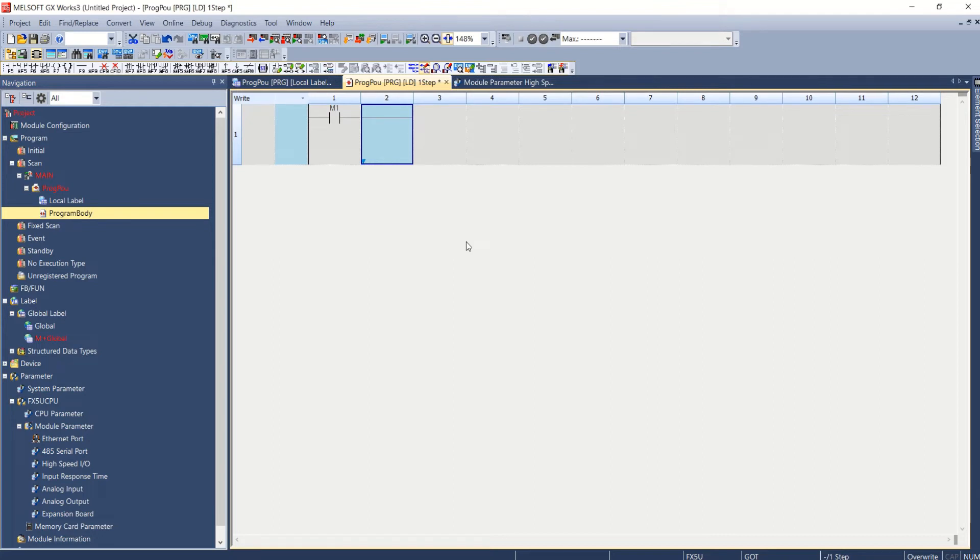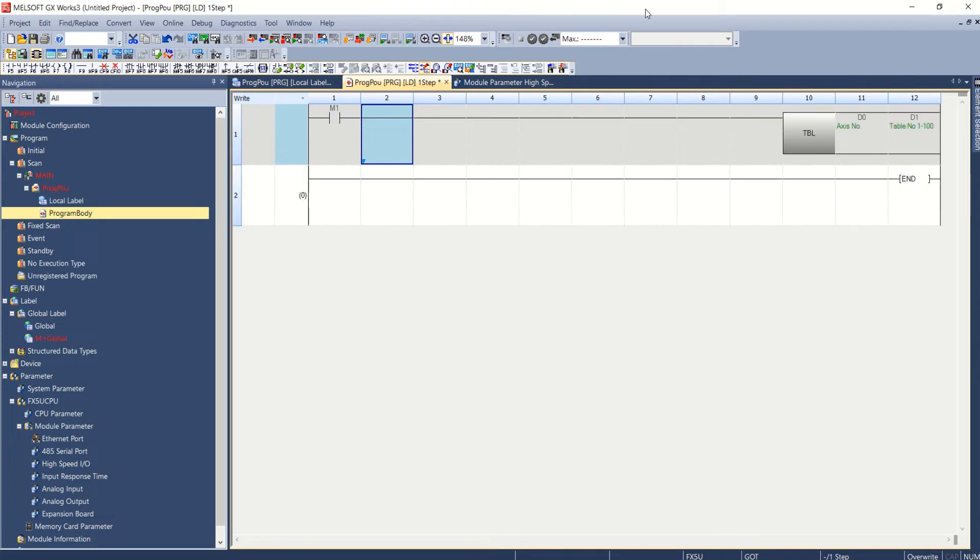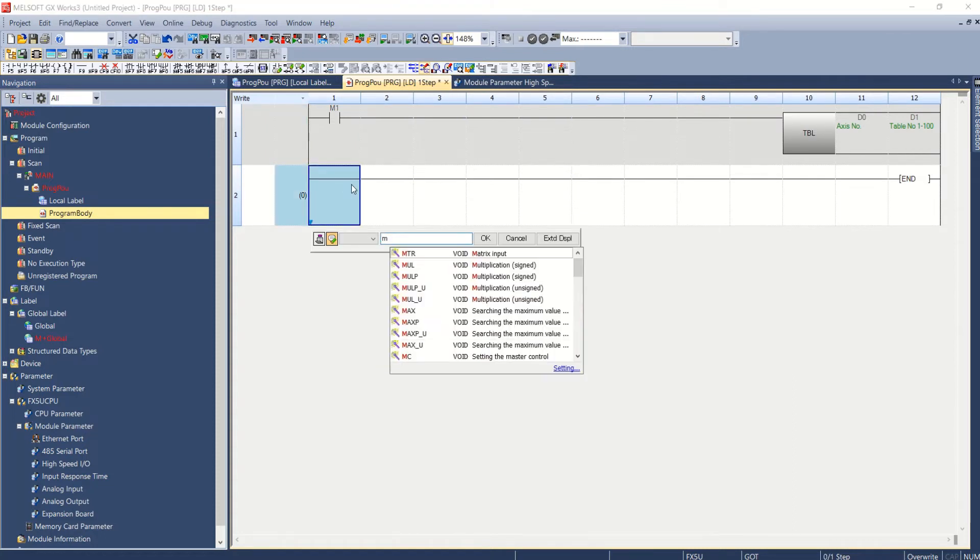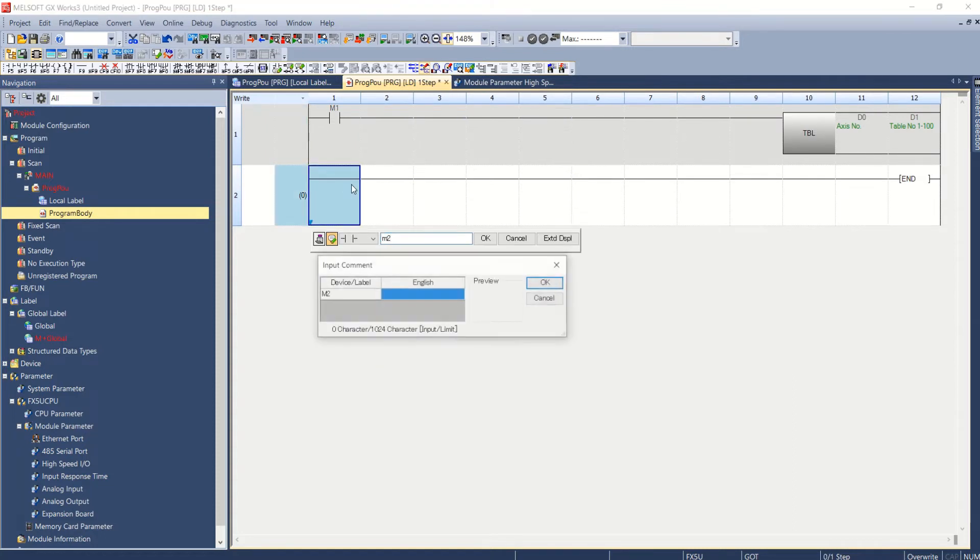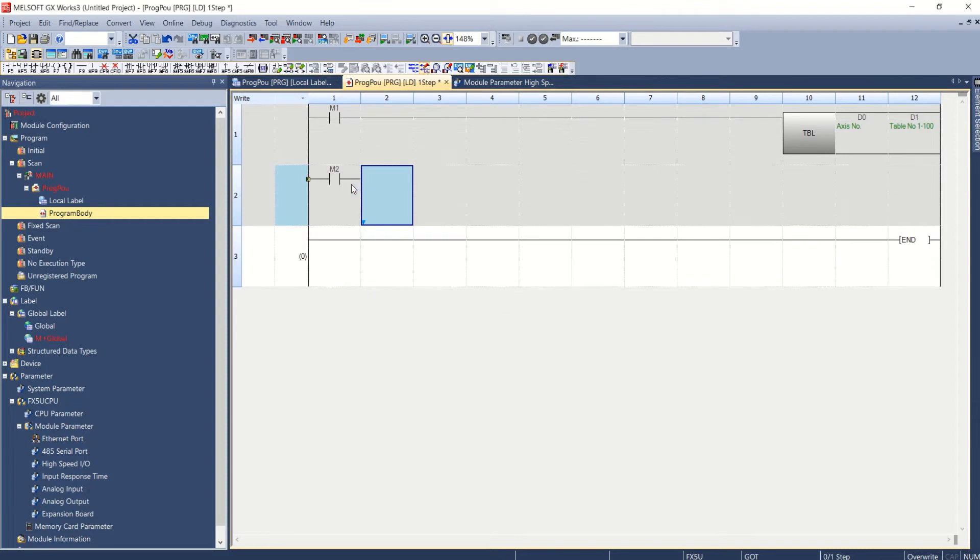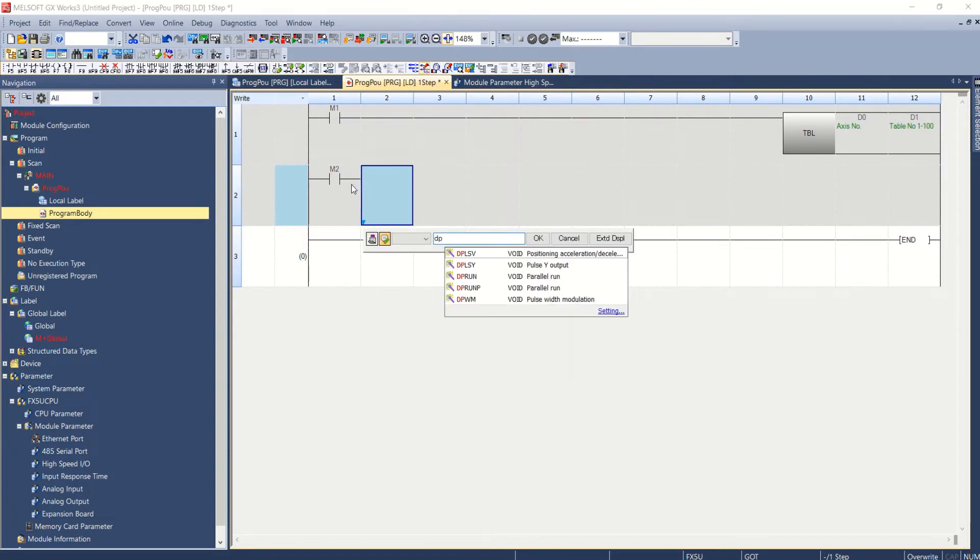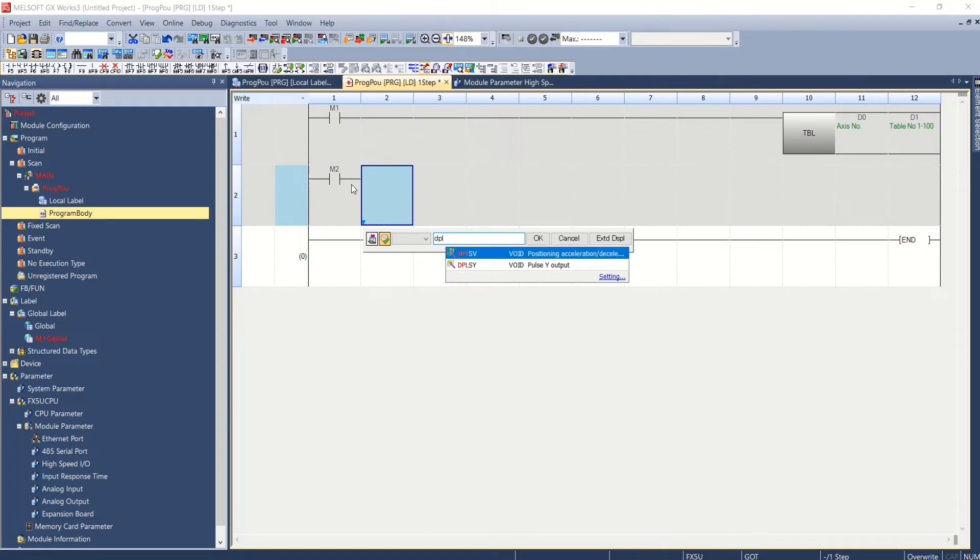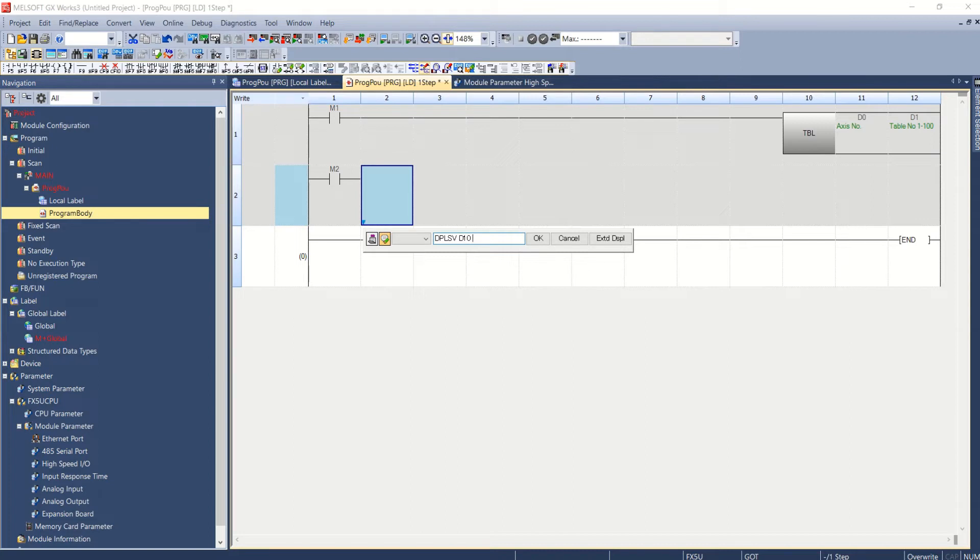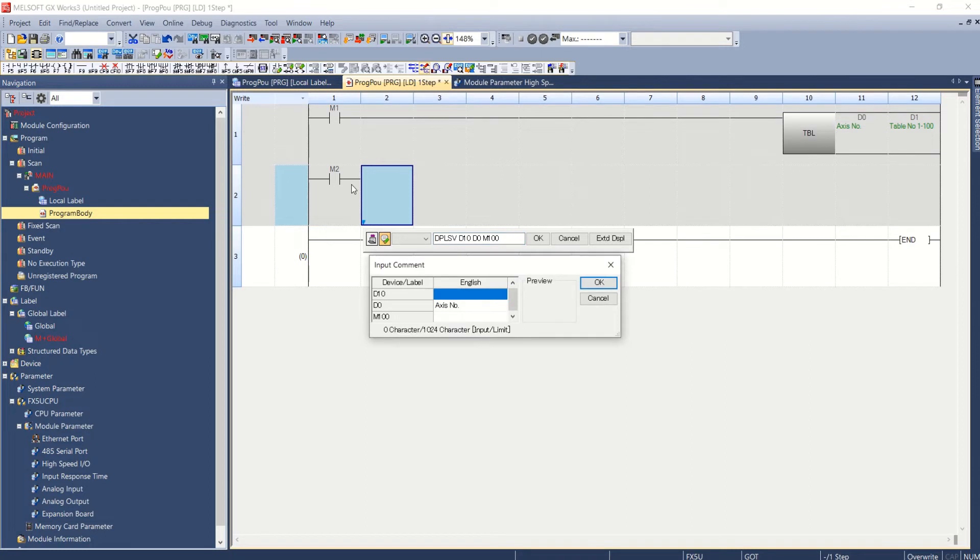Now if you do not use table format then for variable speed operation we can use DPLSV instruction. For variable speed operation that is DPLSV instruction with D10 as command speed, D0 as the axis number and M100 as status. This is command speed.